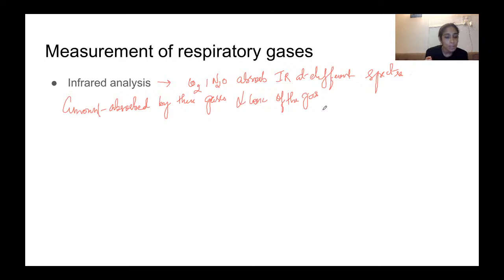Okay, so non-polar molecules like nitrogen, argon, oxygen, helium, xenon do not absorb infrared light, as I have already told you. They cannot be measured by this infrared technology. This method cannot remove the radiation that falls between absorbing lines because of continuous emission that is occurring. Okay, leave that. Most of the infrared measurement units in use today recognize the agent that can be monitored with this technology.